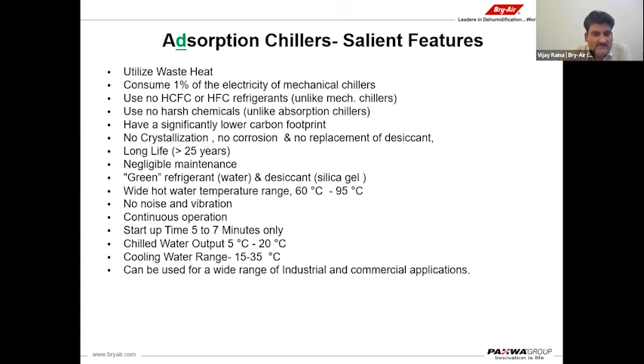There is no noise and vibration since there is no compressor and no pumps installed on the adsorption chiller. This is a continuous operation with changeover from cooling and heating chamber in the middle chamber, but at the bottom of the chiller we generate the chilled water continuously. Startup time is only 5 to 7 minutes, and the chilled water temperature range is 5 degrees to 20 degrees. For cooling water, we can use 15 to 35 degrees as an inlet. This can be used for industrial and commercial applications.